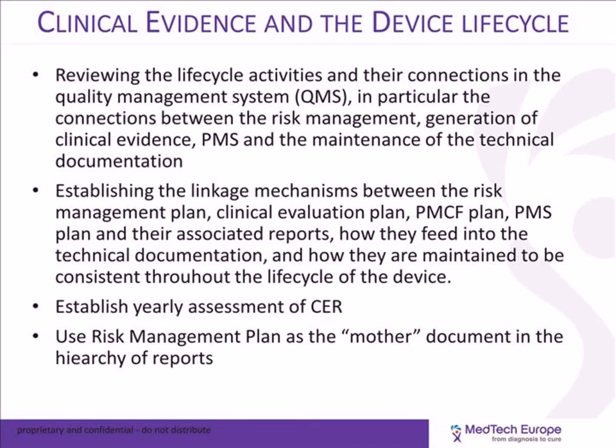This is not a cost for obtaining the MDR. This is a maintenance cost, and the workload should be identified and built into the product maintenance cost well ahead of the MDR. And also, we believe as a group that the risk management plan is in fact the overarching document, that all documents feed this one, and that we need to make sure they are interlinked.